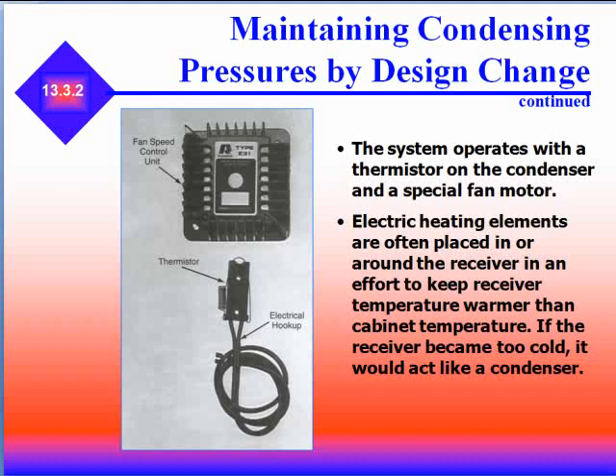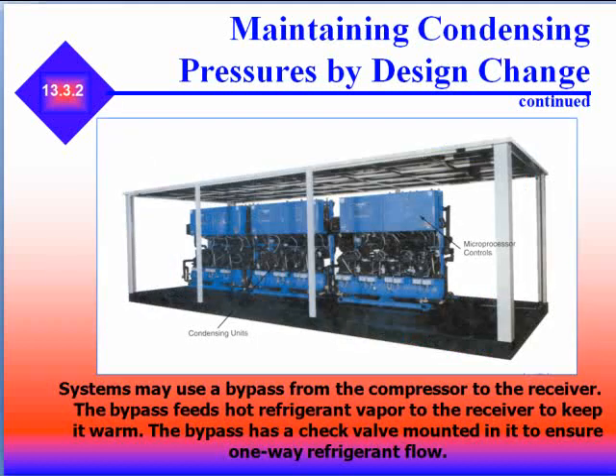The system operates with a thermistor on the condenser and a special fan motor. Electric heating elements are often placed around the receiver to keep it warmer than the ambient temperature. If the receiver became too cold, it would act like a condenser. Systems may also use a bypass from the compressor to the receiver — the bypass feeds hot refrigerant vapor to the receiver to keep it warm, and the bypass has a check valve to ensure one-way refrigerant flow.